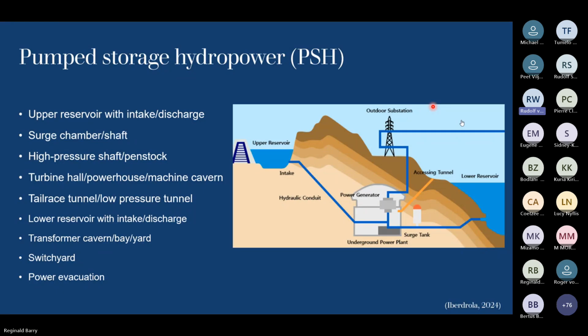Similar to the hydropower plants, you also have problems with surge. If you look at the underground power plant that sits in the middle, you have the low pressure pipeline coming in from the dam, but if that pump stops, you have surge, so you need a surge tank there. You'll also need to do a surge analysis on the actual penstock leading up to the upper reservoir if the turbine trips, etc. But in this case, the upper reservoir is actually acting as the surge chamber, so to speak.